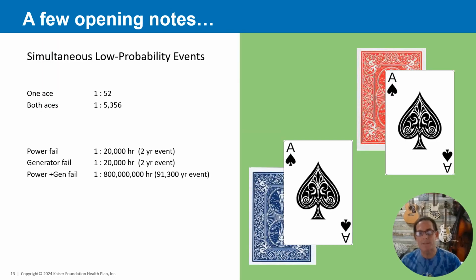The second little topic that we have to talk about is this one, and this is called simultaneous low probability events. So the rule here is that if we care at all about money, then we do not plan for simultaneous low probability events. Allow me to explain. The odds of pulling the ace of spades out of one deck of cards is 1 in 52. If you had two decks of cards right next to each other, the odds of pulling the ace of spades out of both of those decks is 1 in 2,700. Without getting into the math on how to stack probabilities, that is the square. 2,700 is 52 squared.